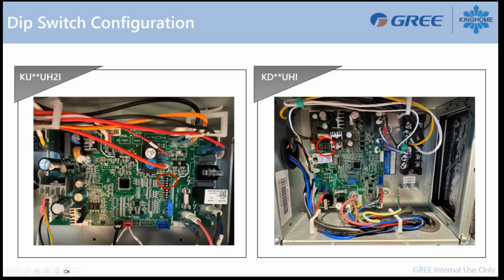we have dip switch located on the top left here, and we have another set in the middle of the board. So the dip switch located in the middle here is the same as those ones. So you don't have to touch those ones. Only the top here will apply the configuration. You will apply the configuration here for your speed adjustment.